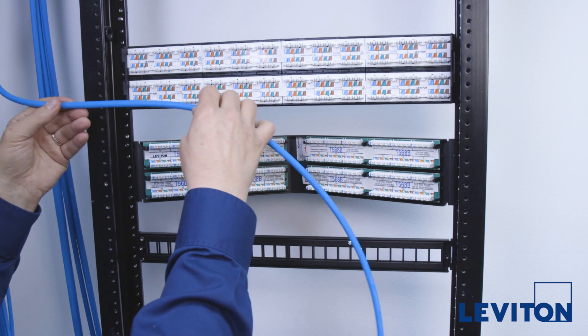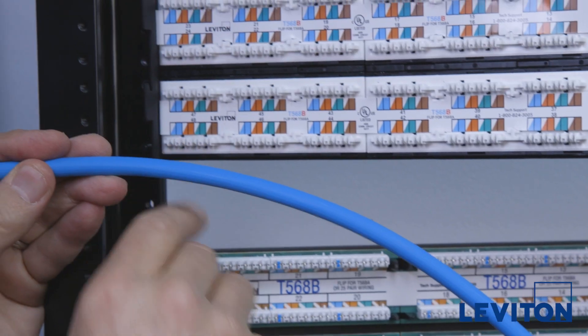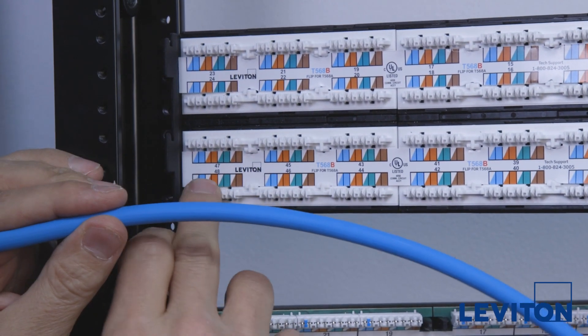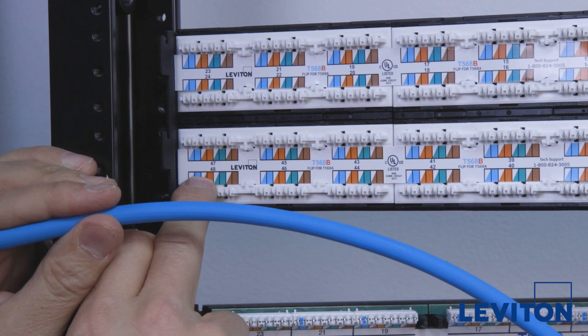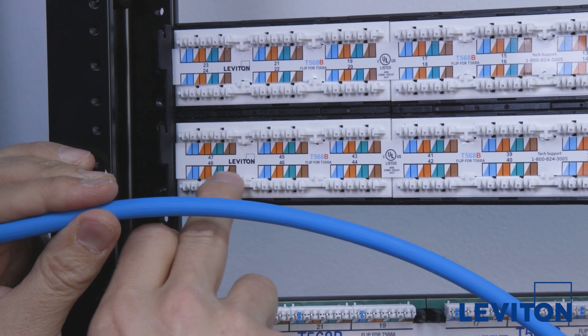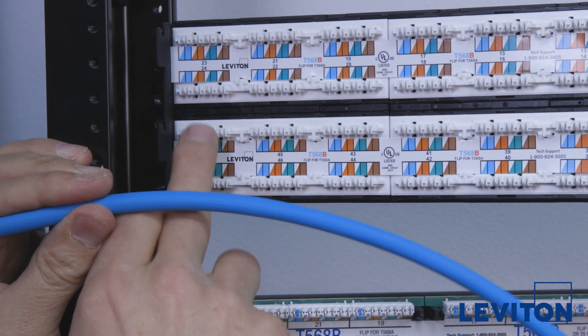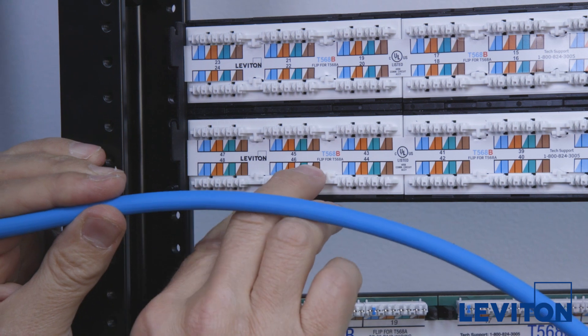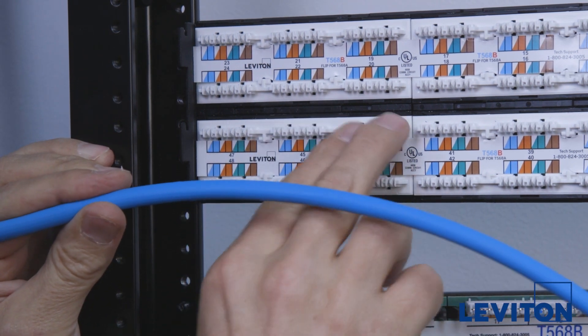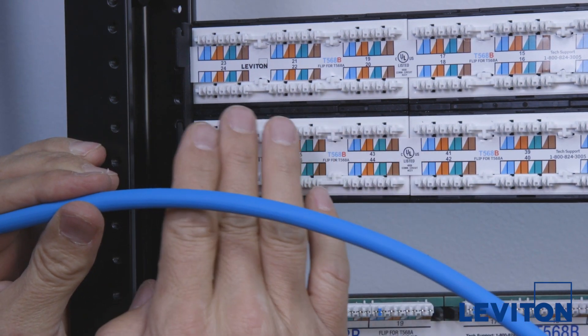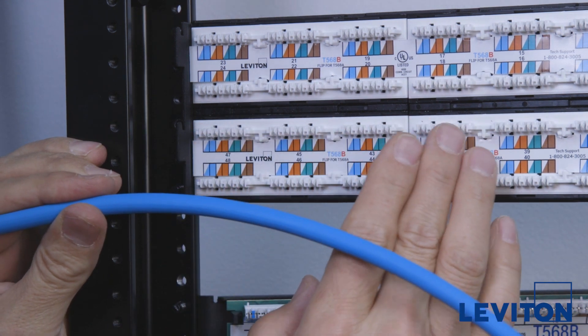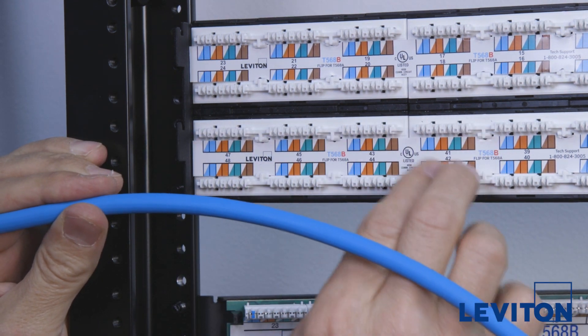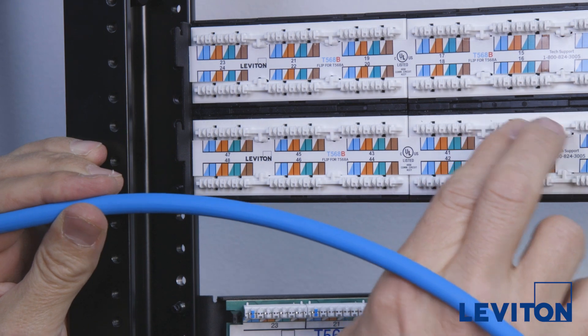Using the Category 6A cable from the left side of the rack, terminate the bottom outboard connector on the left side of the flat Category 6A panel first. Following this, terminate the top outboard connector, then the second connector on the bottom, then the second one on the top, and so forth. Following this zigzag pattern allows you to build up the cables in a way that maintains the best possible organization.